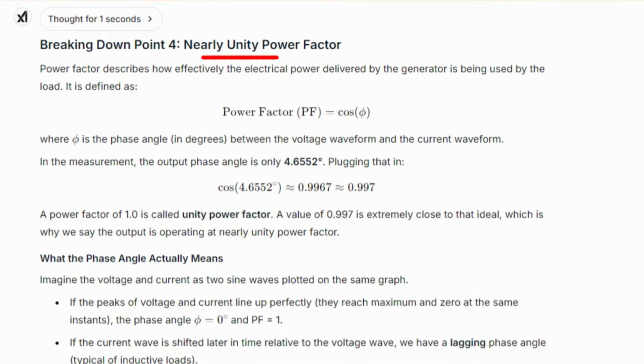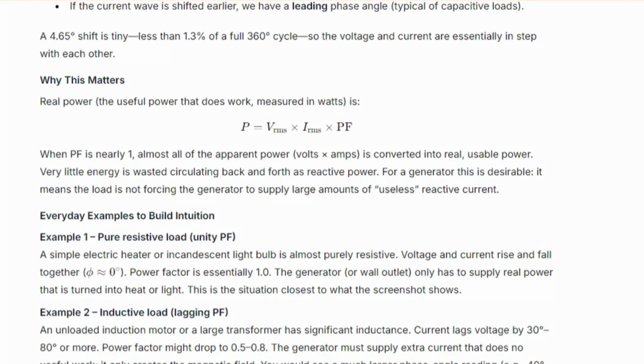Nearly unity power factor. The power factor describes how effectively the electrical power delivered by the generator is being used by the load. It is defined as power factor equals cosine phi, where phi is the phase angle in degrees between the voltage waveform and the current waveform. So the output phase angle plugged in equals 0.997, very close to 1, called the unity power factor. We would say that it is extremely close to that ideal, meaning the output is operating at nearly a unity power factor. When a power factor is nearly 1, almost all of the apparent power, volts times amps, is converted into real usable power. Very little energy is wasted circulating back and forth as reactive power. For a generator, this is desirable. It means the load is not forcing the generator to supply large amounts of useless reactive current.